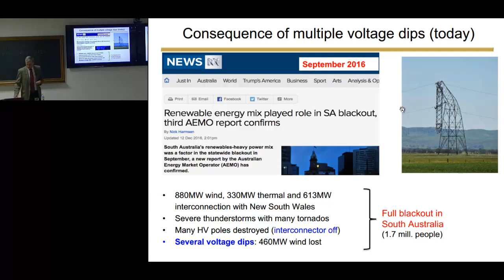There was software that, after a few voltage dips, disconnected the turbines. So they withstood the first voltage dip, but not quite a few. At the end, there were several voltage dips, a disconnection of wind energy, in combination with the interconnector also being switched off. So at the end, there was a big blackout in Australia because of the voltage dips. This was last year.